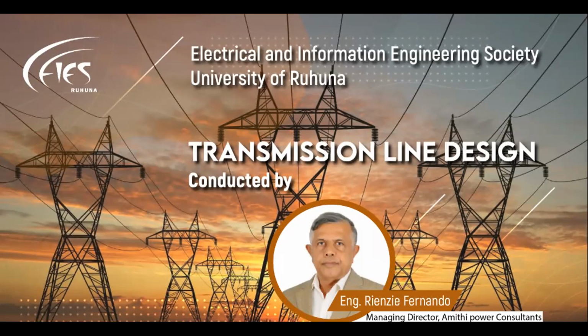Hello, sir. I'm Ramal. My question is, when considering the creepage distance, as you mentioned, it depends on the pollution level, right? So in Sri Lanka, my question is, for a transmission line which is close to the sea area, is it still enough to use 25 millimeter per kilovolt creepage distance? Because in the sea area, we have salt pollution.